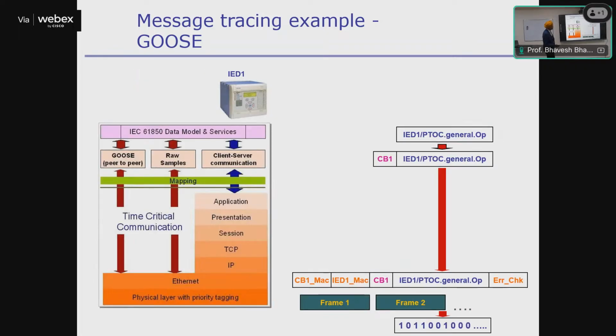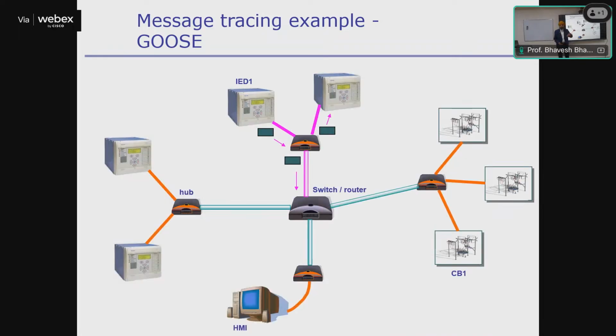IED1 is going to issue the trip command. So IED1 protection general operation, it's for circuit breaker 1, and then it appends the MAC addresses - that's it, nothing else. Then we have the same thing; it basically goes directly through the link layer. So this is what will happen: IED will issue the command for circuit breaker 1.